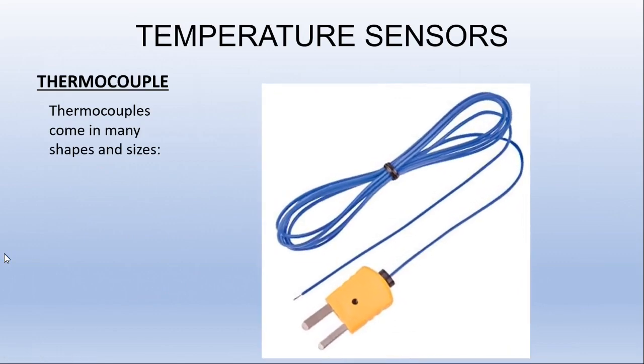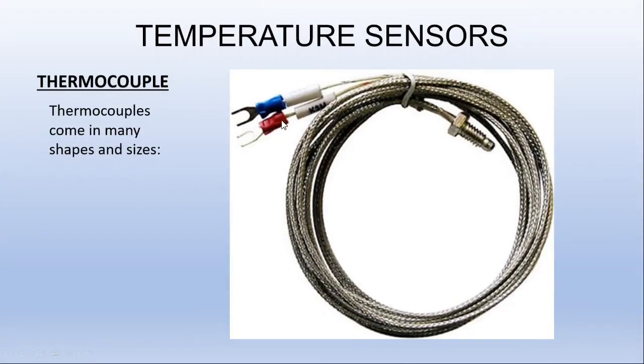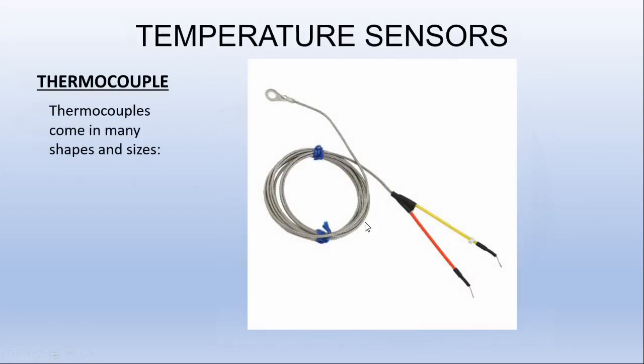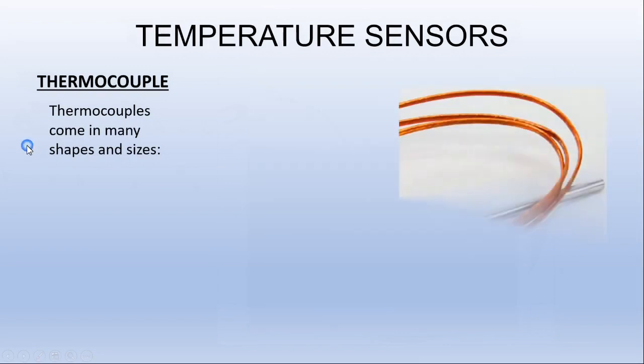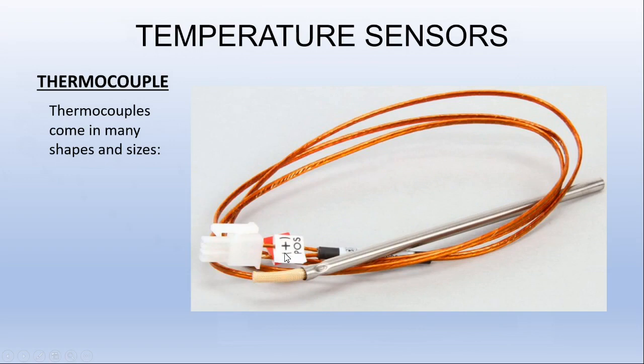So here we have a picture of one that's probably used for a meter. It's a bead probe, and these terminals, one wider than the other, obviously would be for the sake of polarity. You can barely see the positive and negative there. That would be plugged into a meter. Here's one that's got color-coded connections on it, and it probably would indicate positive and negative somewhere, and a screw-in button, probably for a surface sensing device like a flat-top grill. Here's another one with a surface sensing type of thing with a lug type connection. So notice the color differences. And here's one that says positive, so obviously the other was negative, and it just looks like a regular probe. Your probe tip is in here, the sensing element.